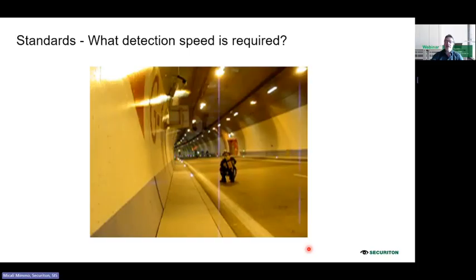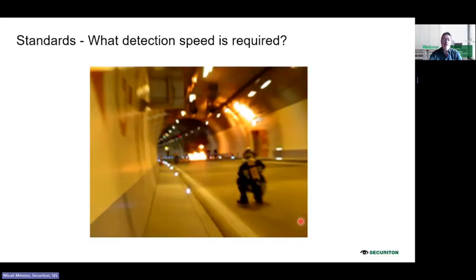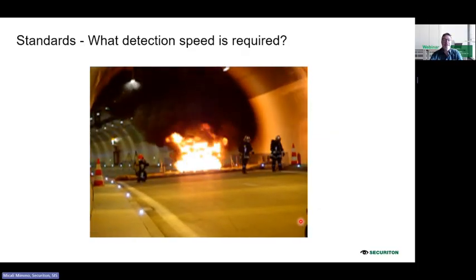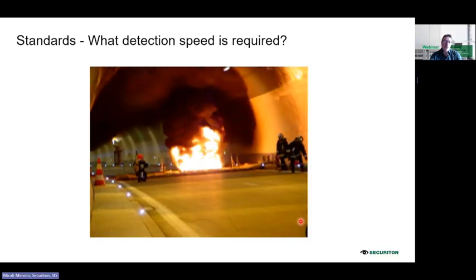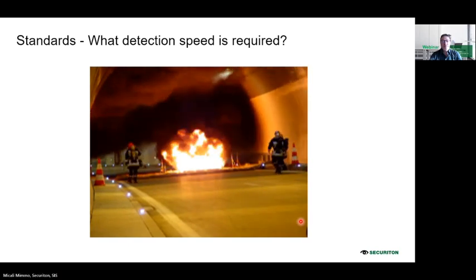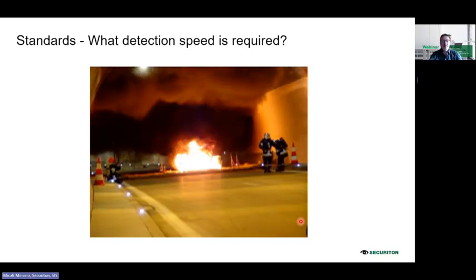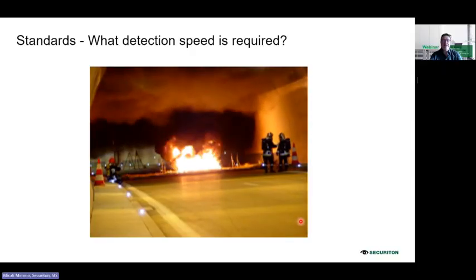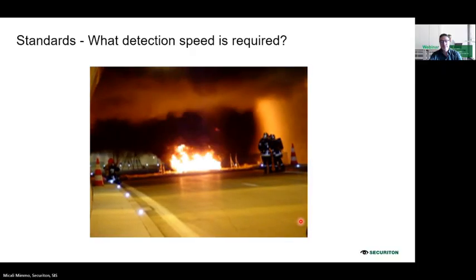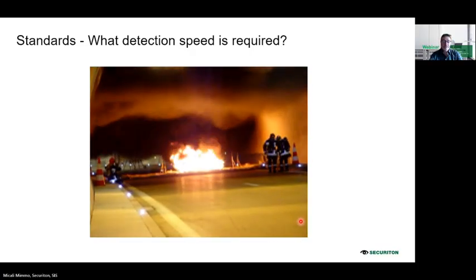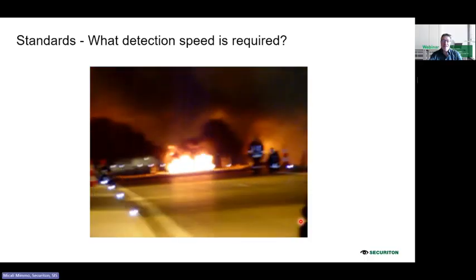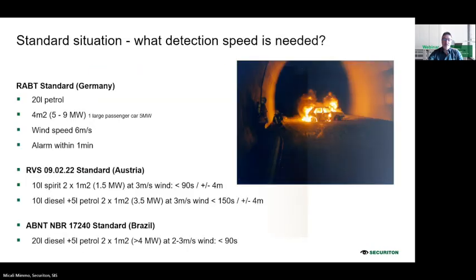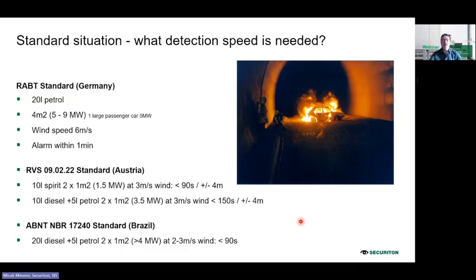This video shows fire brigades doing some tests. We will see now this test according to the local requirements. Usually it's a test done with 10 to 20 liters of petrol. And you see how fast the smoke is going up and expanding. The fire detection system is not triggering an alarm. That means the ventilation system did not start the de-smoking. And you see in a few seconds, there's no visibility. Even the cameraman, you see, was also surprised. They are used to doing fire tests in tunnels, but he was surprised that the smoke came down very quickly.